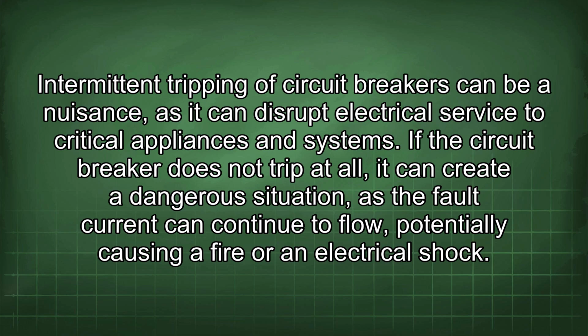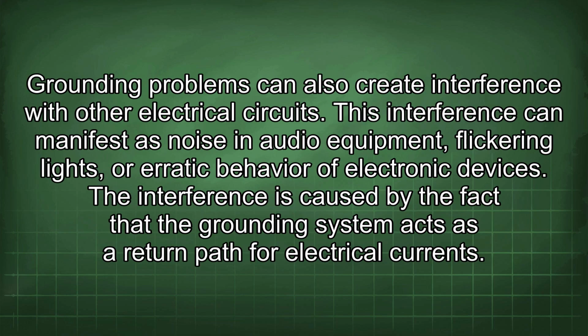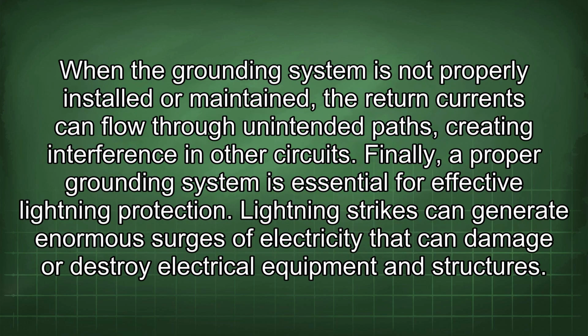Intermittent tripping of circuit breakers can be a nuisance, as it can disrupt electrical service to critical appliances and systems. If the circuit breaker does not trip at all, it can create a dangerous situation, as the fault current can continue to flow, potentially causing a fire or an electrical shock. Grounding problems can also create interference with other electrical circuits. This interference can manifest as noise in audio equipment, flickering lights, or erratic behavior of electronic devices. The interference is caused by the fact that the grounding system acts as a return path for electrical current. When the grounding system is not properly installed or maintained, the return currents can flow through unintended paths, creating interference in other circuits.